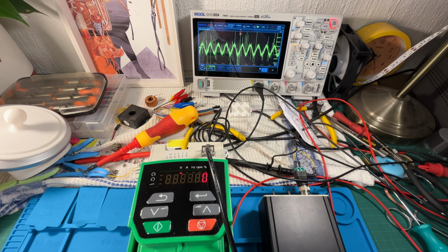That's usually done on constant power loads as well. You're not going to achieve this on a square law load. It doesn't work very well, because obviously a square law load is going to be demanding more power exponentially at that point, and you're in constant power, so it's not going to work. It's something like a conveyor that you just need to overspeed a little bit. Maybe your gearing or something isn't quite right, or the operating conditions require it, and then you overspeed it and it works. It's not a problem. So that's the story.